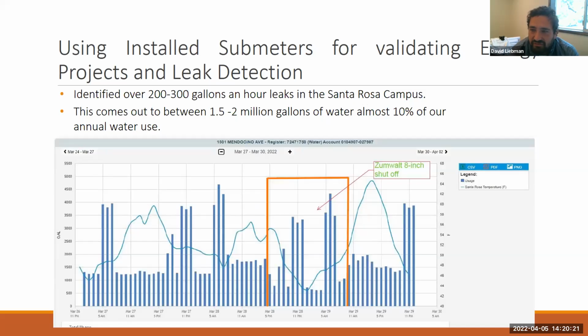Lastly, again using sub-meter data, we're doing more targeted approaches to look at water, especially in our drought conditions. We've currently identified on the Santa Rosa campus between 200 to 300 gallons an hour in water leaks in our old 8-inch water mains. We're beginning to use our sub-meter data to isolate our water use and valve off certain sections of our infrastructure when no one's around, on weekends or during spring break, to find out where these leaks are, with the hope that once identified we can address it. It's looking like between 1.5 to 2 million gallons of water a year, almost 10% of our water use, is going into leaks through our old 8-inch lines, originally installed back in the 70s. This is the targeted approach to sustainability that we're only able to do because we've installed sub-meters and can analyze this data.